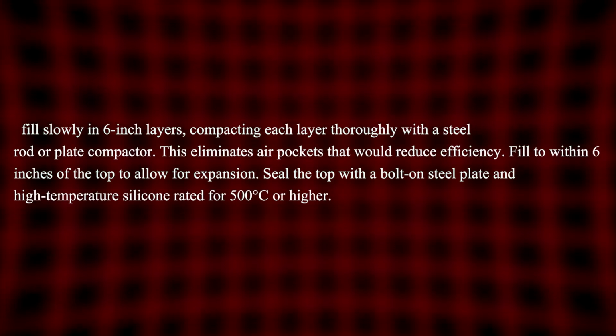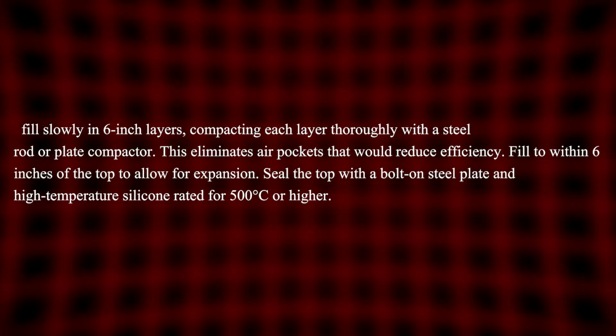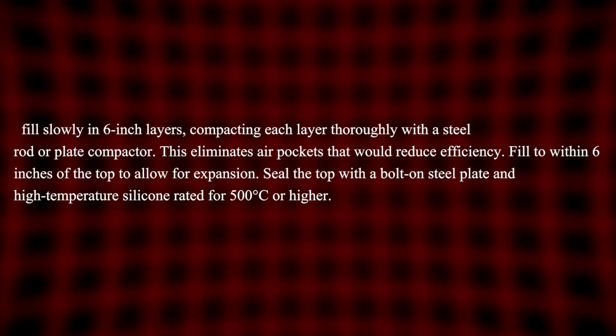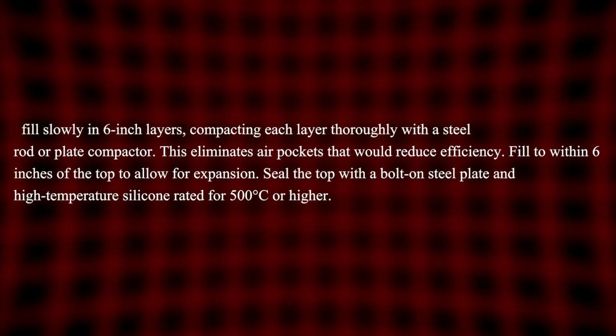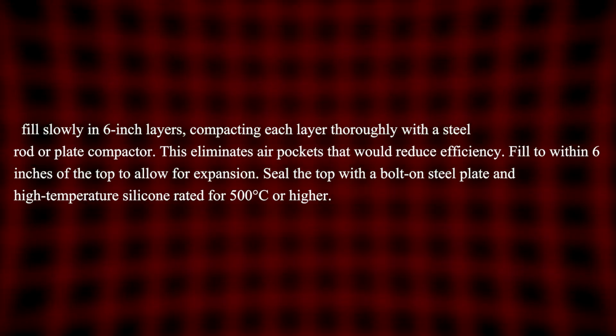Second, fill slowly in 6-inch layers, compacting each layer thoroughly with a steel rod or plate compactor. This eliminates air pockets that would reduce efficiency. Fill to within 6 inches of the top to allow for expansion. Seal the top with a bolt-on steel plate and high-temperature silicone rated for 500 degrees Celsius or higher.